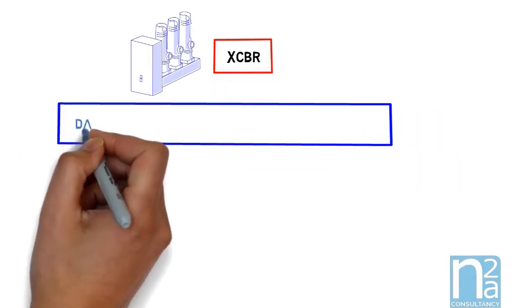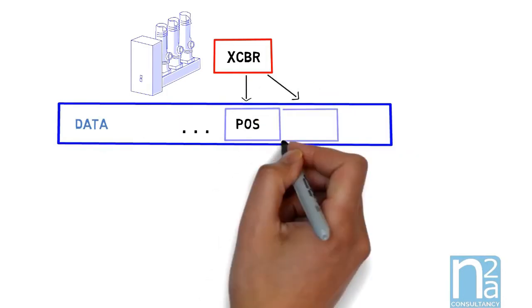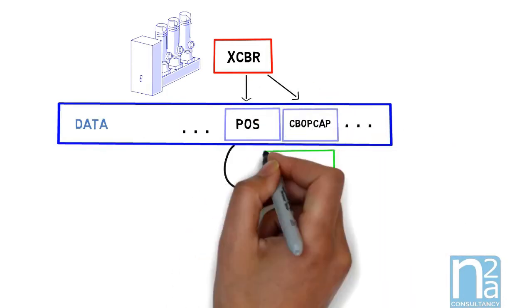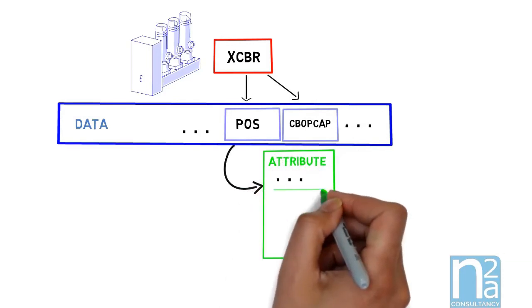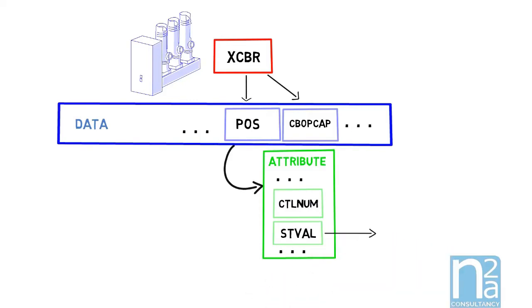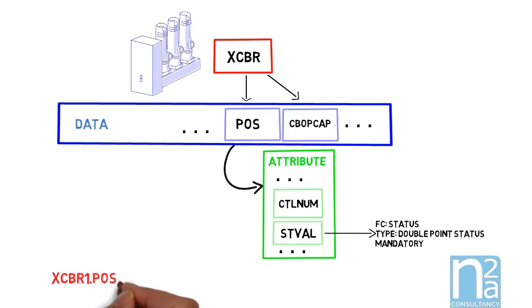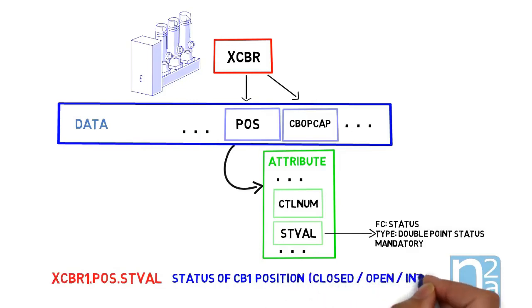Each logical node contains a certain number of data. For example, a circuit breaker has a data called Pos which represents its position. Data has data attributes which specify parameters. Here we have stVal which represents the status value of the position: closed, open and intermediate. Data attributes belong to a function class, for example here it is a status. Data attribute also has a type, here it is dbpos, double point status: open, close, intermediate. And it is specified if this attribute is mandatory, optional or conditional. This one is mandatory. It means that every vendor should implement this data attribute in their IEDs.